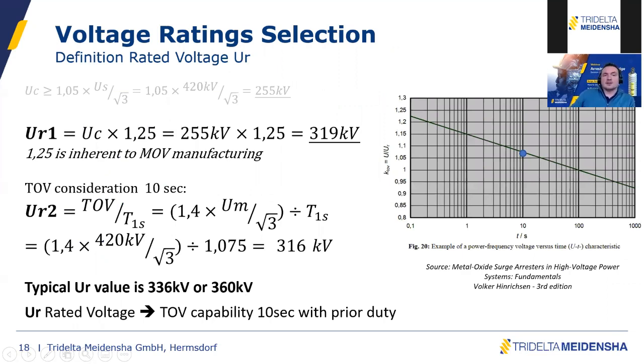Then comes the selection, or the definition, of the rated voltage, UR. So we need to consider, in that case, the MCOV. As you can see, there are two possibilities, and that's why you have UR1 and UR2. The first method is quite simple. It's a factor of 25%, which is a well-accepted factor coming from the MOV manufacturing, or MOV properties, would be better to say, because I will develop a bit further, but a rated voltage is actually a temporary overvoltage.